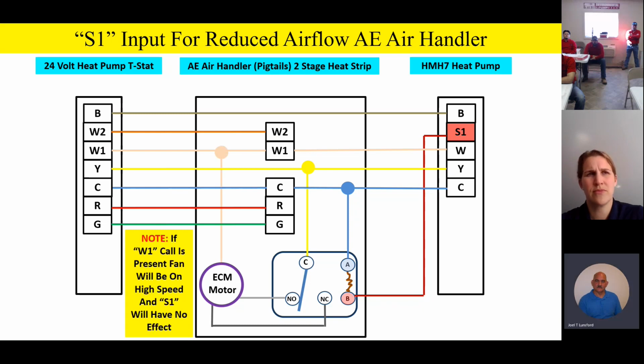Now, it should be noted, if I get a W1 call during this time, so let's say we're at reduced airflow, and I get an auxiliary heat call, and that indoor blower motor, that ECM blower, has a high-speed command. Well, hang on a second. The high-speed command is greater than the S1 command we have right now with reduced airflow, which is actually 65% airflow. It will automatically drive that motor to high speed. Because remember, anytime you have an ECM motor with more than one speed tap being commanded at one time, it will always go to the highest speed tap that's being commanded. So an example would be if I had a W1 auxiliary heat call, bang, it'll go ahead and just go to that speed tap because it's a higher speed tap.